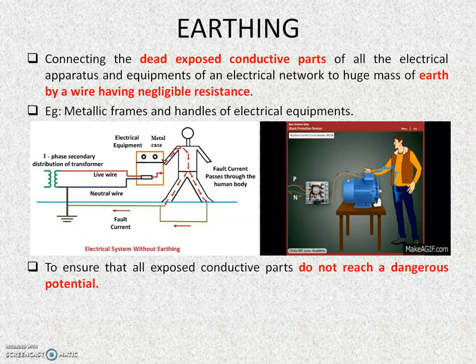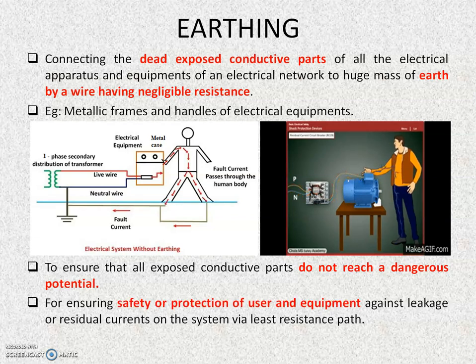Thus, to ensure that all exposed conductive parts do not reach dangerous potential, earthing is done. How this is done and how it protects the operator we will discuss in the next slide. So the earthing ensures safety or protection of user and equipment against leakage or residual currents on the system via a least resistance path. And it provides a safe path to lightning and short circuit currents as well.